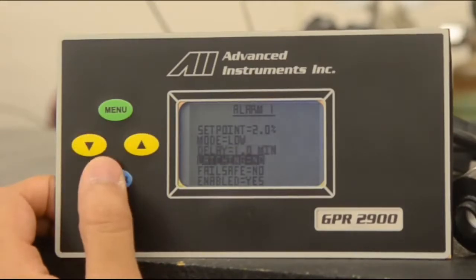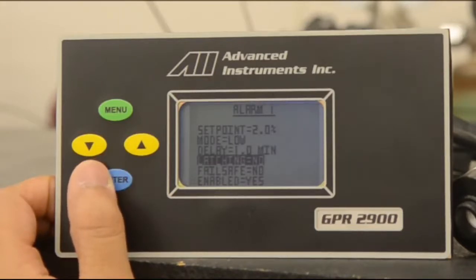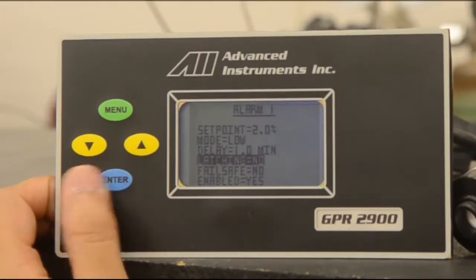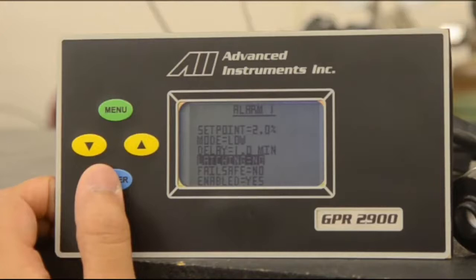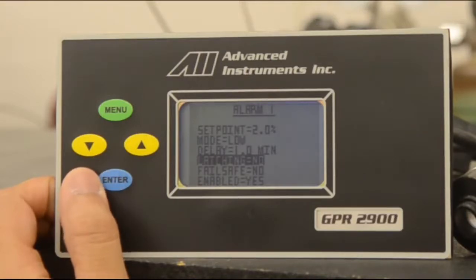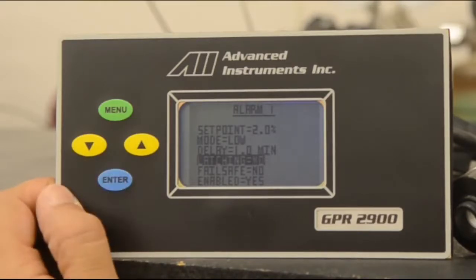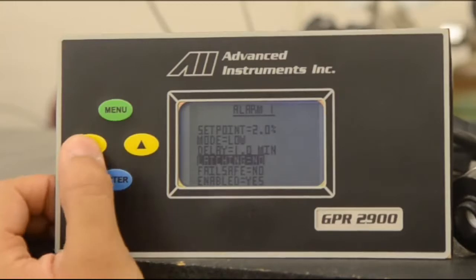You also have the option of latching alarms. This allows the alarms to, once energized, stay energized until a user physically comes to the unit and releases the alarm. This will de-energize the relay and allow the system to go back into a non-alarm state. Hit enter for yes, again enter for no.